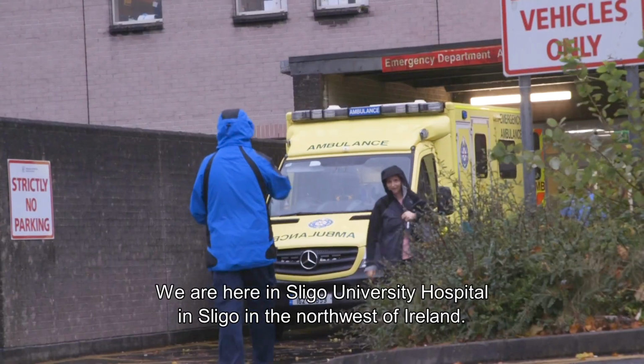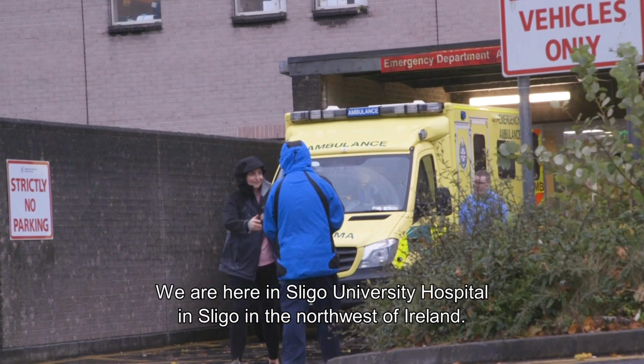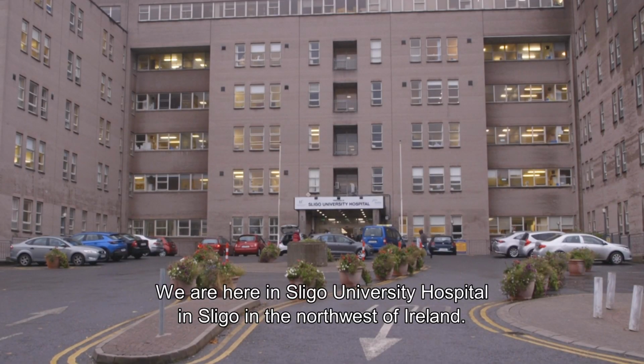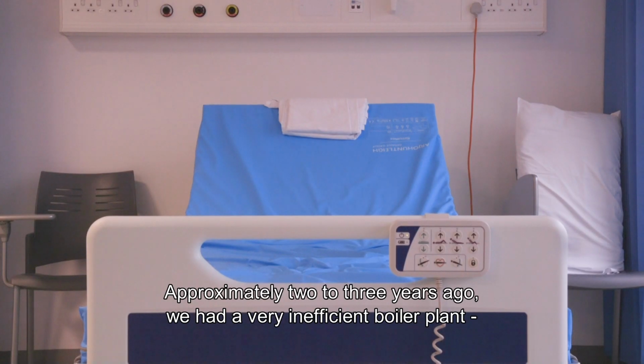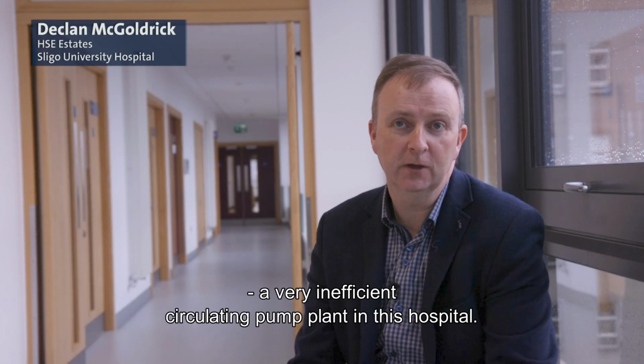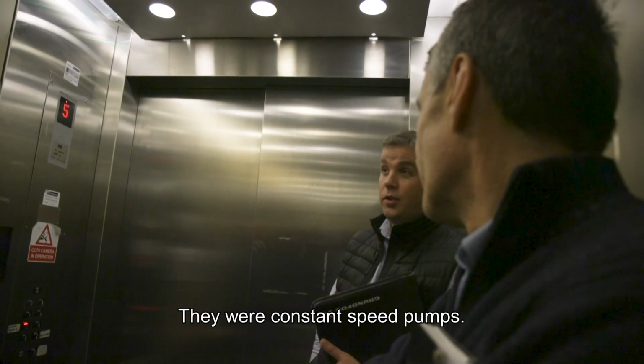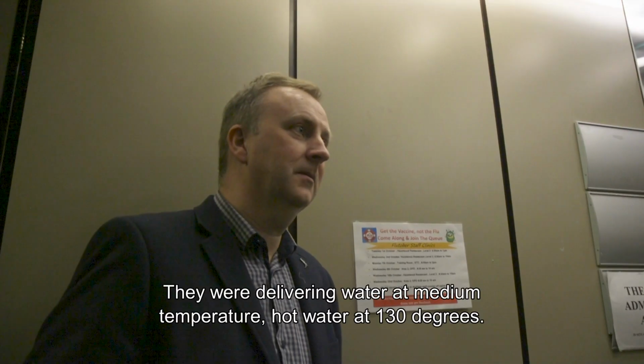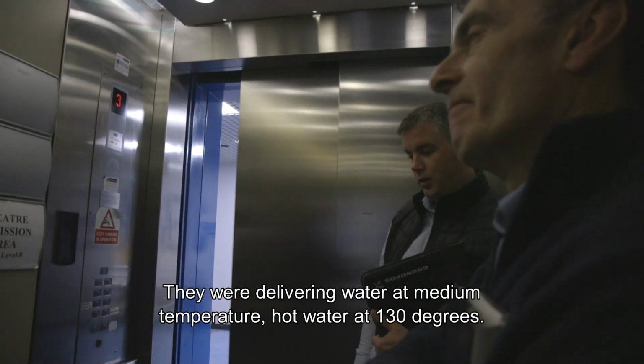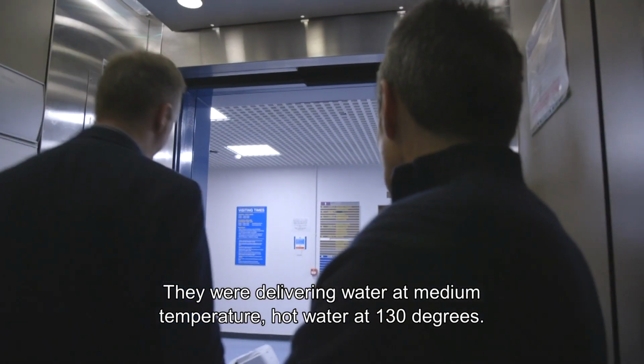We are here in Sligo University Hospital in Sligo town in the northwest of Ireland. Approximately 2 to 3 years ago, we had very inefficient boiler plant, very inefficient circulating pump plant in this hospital. They were constant speed pumps. They were delivering water at medium temperature hot water here at 130 degrees.